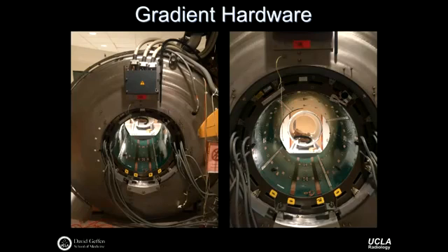And the gradient coil has a few things attached to it which are of note. One is up on top here is the power supply. And what you'll notice is not the power supply per se, but the cables that provide the power. And what you might notice about these cables is that they're about as thick as my arm, right? They're carrying huge amounts of relatively high current, very high voltage. We need very high voltage to generate the magnetic fields that produce these gradients. So large amounts of voltage coming in through these cables here, they're very big. Like I said, this is the gradient insert here.